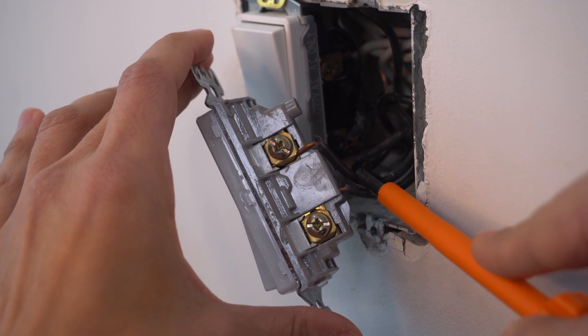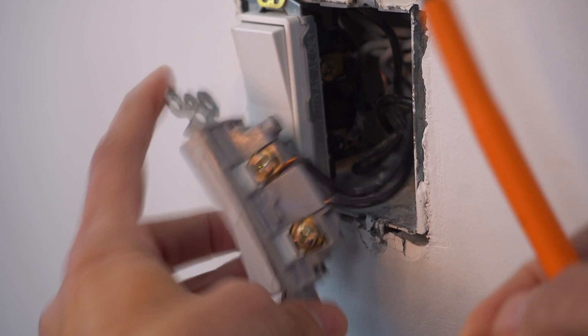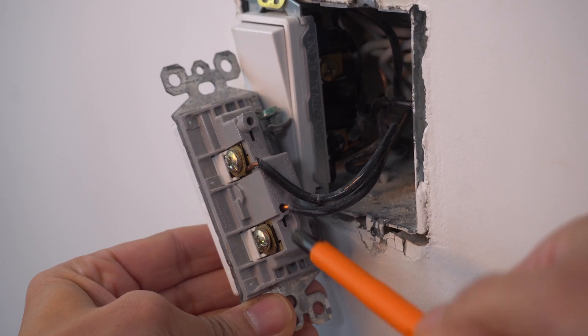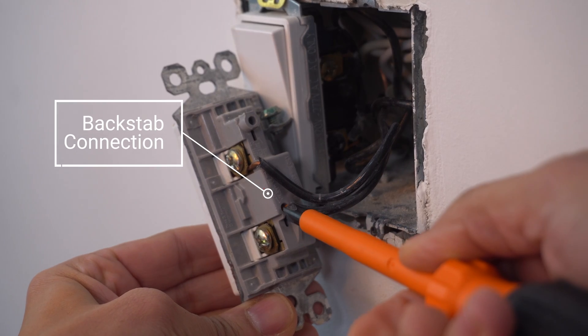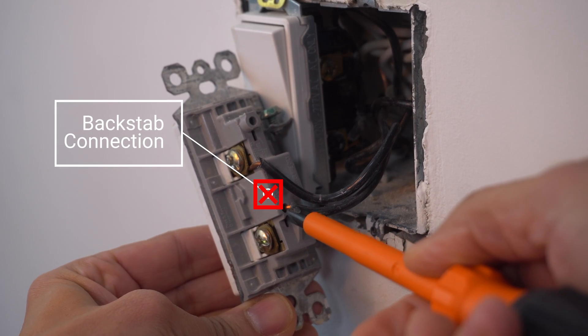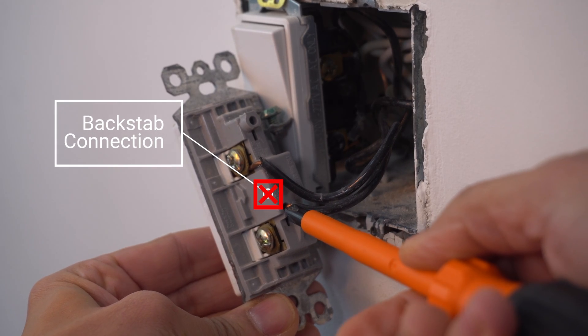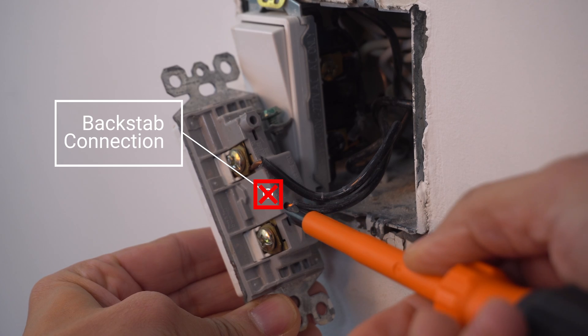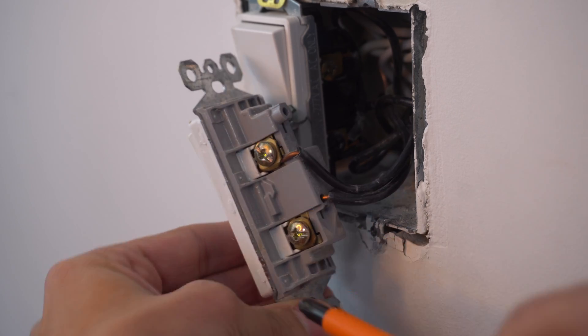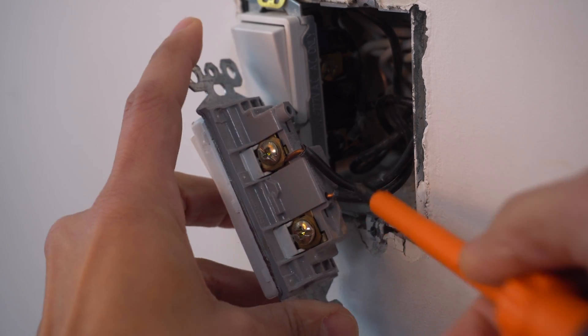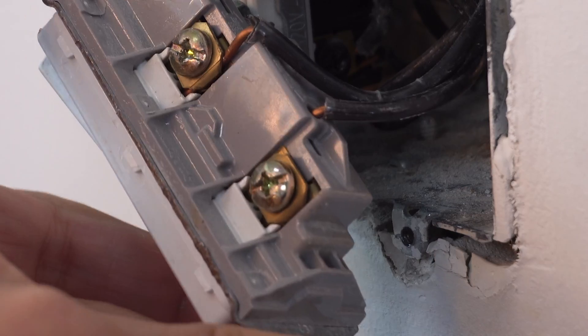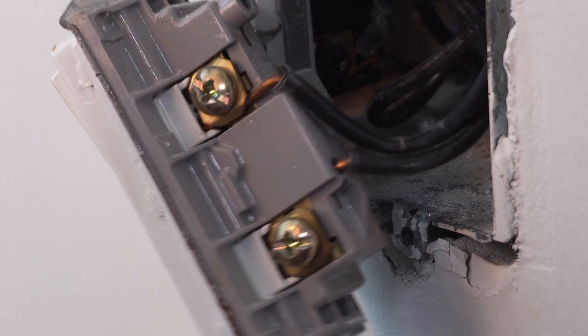but even worse is this is a backstabbed connection, which means the wire is inserted in the back. So this is something that I would remove definitely out of a house and I'm surprised to see here in the first place.